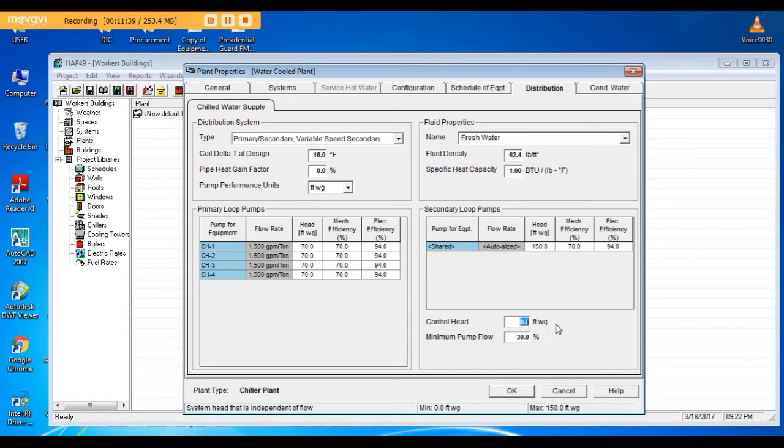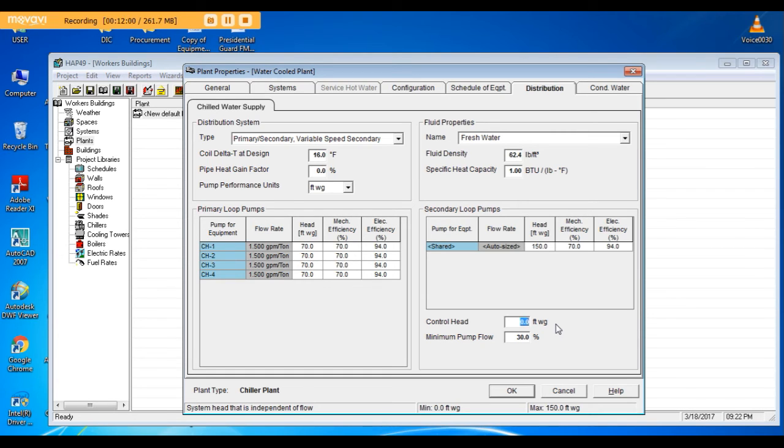Control head: control head means the head required between the supply and return, or in other words the differential pressure between supply and return that you want to maintain and that will control the speed of the secondary pump.